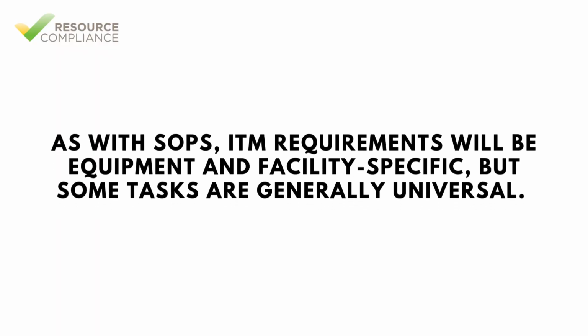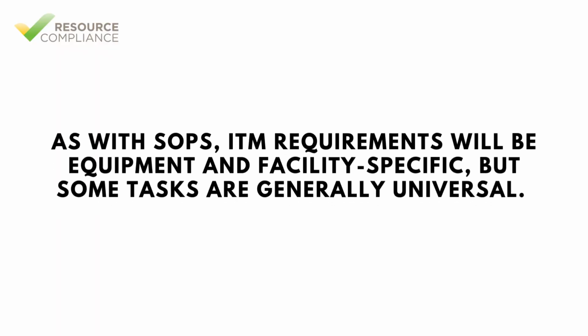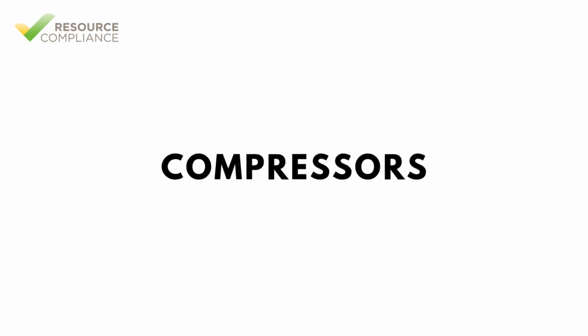So in a sense, there is a bit of a moving target, but it's a good thing, because as an industry, we're always refining, correcting, and focusing our attention on what's important. So it's important that the operator understand this and know which RAGAGEPs they're following. As with SOPs, ITM requirements will be equipment and facility specific, but some tasks are generally universal. Compressors typically require the most ITM attention from an operator.